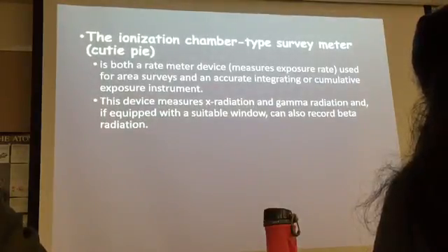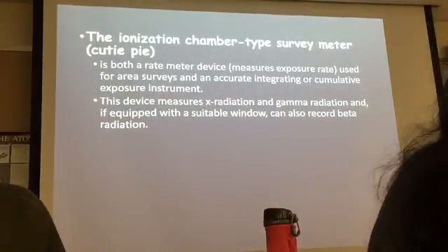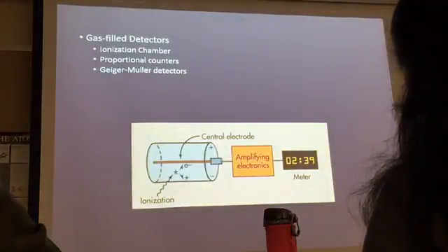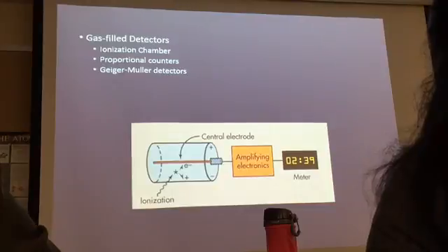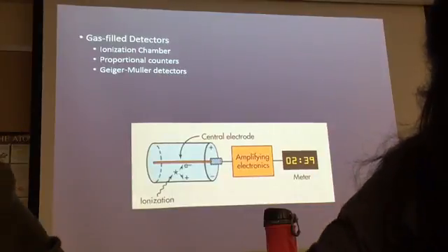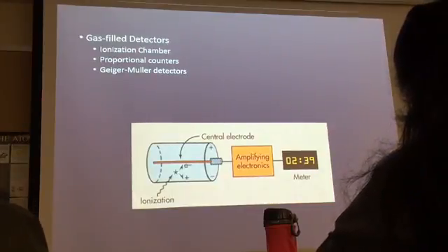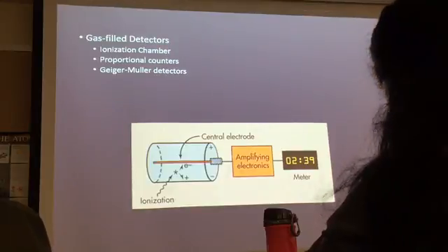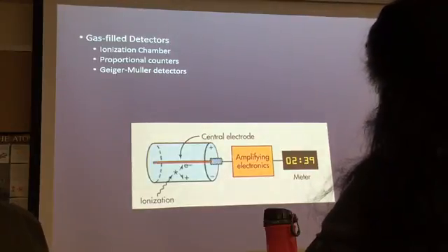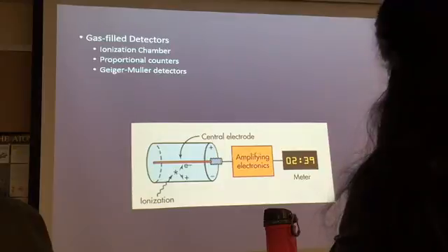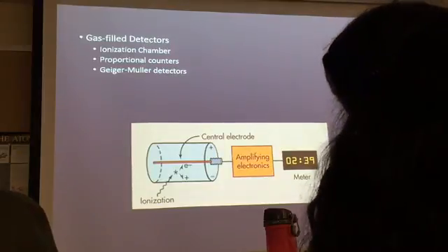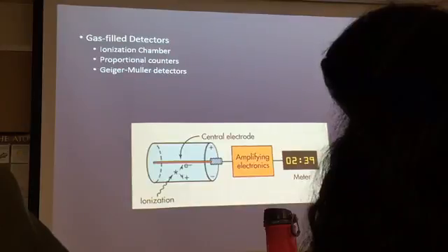This is one example. Ionization chamber. Let me go back here for just a second. Ion chambers or ionization chambers, depending on where they are, if you make them very sensitive, it is possible to detect particles, beta particles at least. For example, the ion chambers we were using the other day are just for electromagnetic radiation.